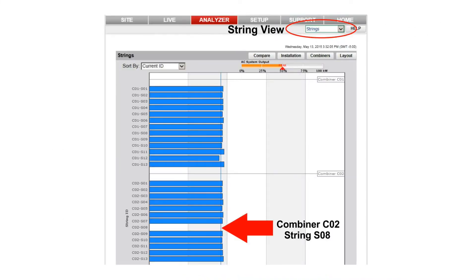For a visual comparison of the string currents in each combiner box, click on Strings in the analyzer pull-down box. It also shows that string 8 in combiner 2 has no output while the other strings are delivering current.